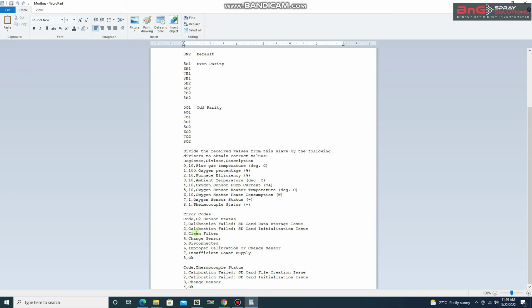So here we will be demonstrating the communication between the Modbus master and the Modbus slave. Modbus slave is the oxygen analyzer, and Modbus master, we are using the simply Modbus master 8.1.2 software. It will be Modbus RTU, and the COM port in our case is 3. The COM port in your case can be as you can check in the device manager. The baud rate, data bit, stop bit and parity should match with whatever you have provided in the SD card file that we demonstrated previously.